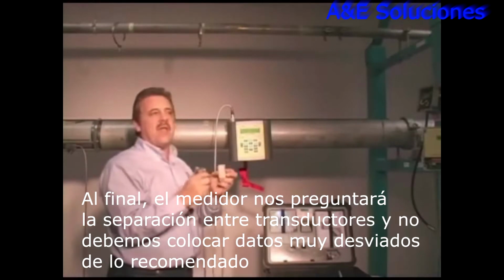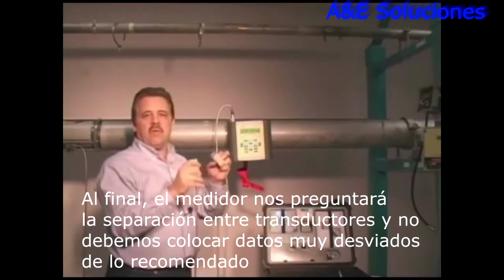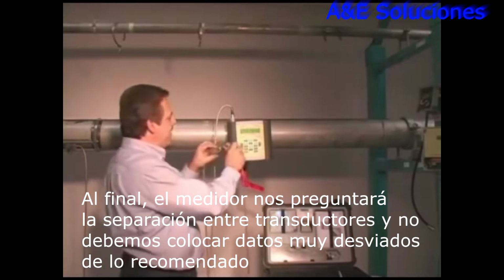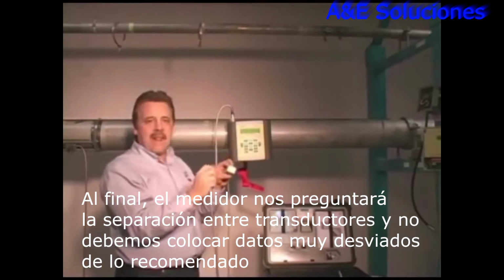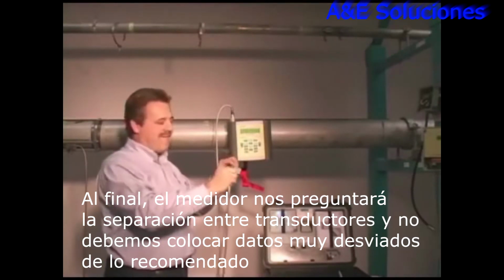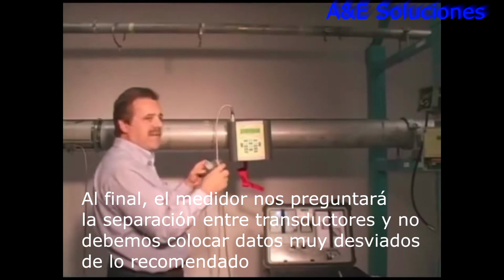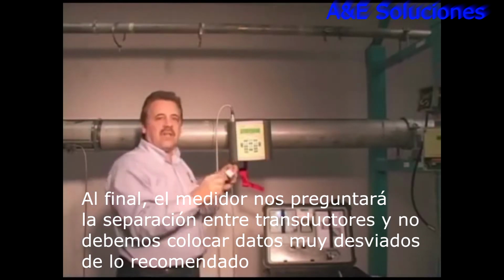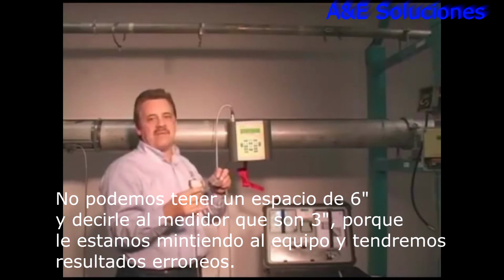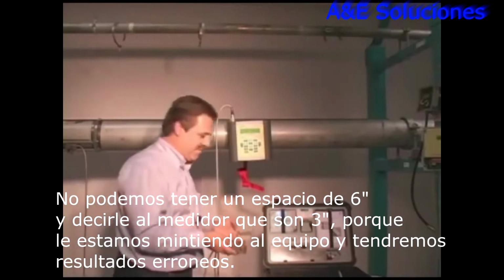And then ultimately the meter will ask us, what spacing do we have it set at, and we tell it. Main thing is that we tell the meter what we spaced it at. We don't deviate too much from what it recommended, and then we tell it what we have it at. We can't have it at a spacing of 6 inches and tell it it's at 3 inches, because now we've lied to the meter and an error is going to result from that.